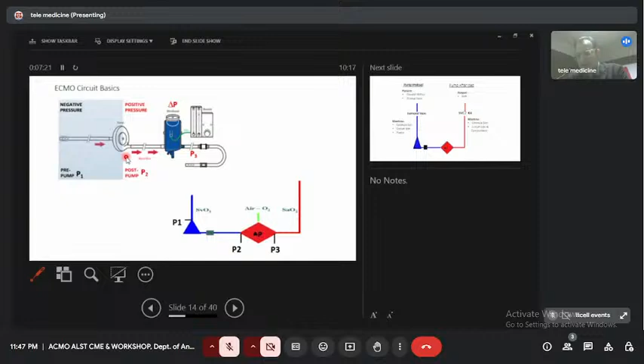So we have to understand these 3 parts of the pressure, and we routinely monitor P2, P3 in a separate monitor. Likewise, you do with your arterial blood pressure, you monitor on your screen. Similarly, you need another monitor in which you can mainly monitor these 2 pressures to calculate the delta P across the oxygenator, right? That will give you any obstructions across it. Fine. So this part is important. I repeat again, there are 3 parts in the pressures in the ECMO circuit: P1, P2, and P3. P1 is pre-pump, P2 is post-pump, and P3 is post-oxygenator. P2, P3 is the delta P that is required to check whether there is obstruction in the oxygenator in the form of clots, because definitely it has got some life, or the action of your anticoagulants, okay. And this P1 pressure has to be negative just to check whether this thing is functioning fine or not, okay.